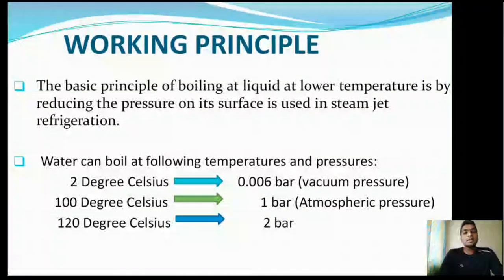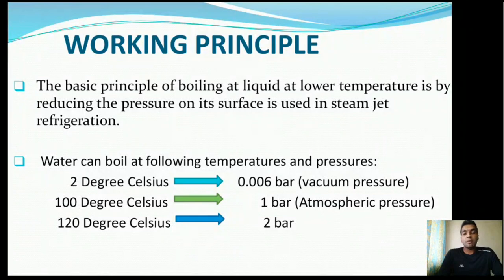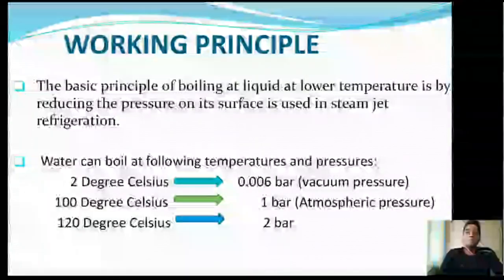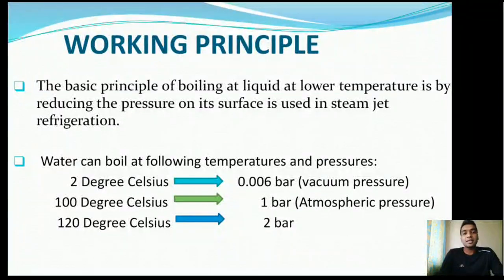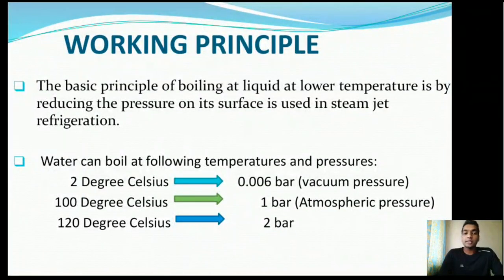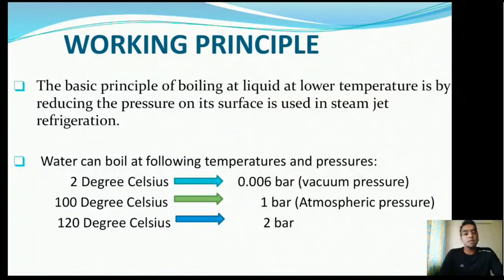Before explaining the working principle, let us understand the third law of refrigeration. It states that the temperature at which a liquid boils or evaporates directly depends upon the pressure to which it is subjected. This means if you reduce the pressure, the boiling point will reduce; if you increase the pressure, the boiling point will increase. For example, water can boil at 2°C at 0.006 bar (vacuum), at 100°C at 1 bar (atmospheric), and at 120°C at 2 bar.